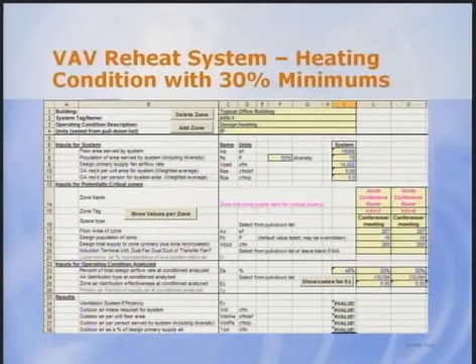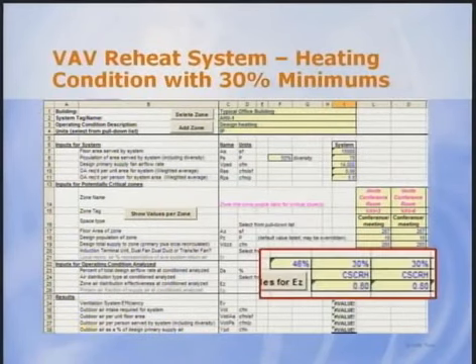First, we'll assume the system is a standard VAV reheat system with 30% minimum set points on the exterior zones. We will assume the interior zones are cooling, but at 75% of their peak, as might occur on a cold morning. On row 23, we enter 30% for the exterior zones and 75% for the interior zones. The spreadsheet automatically determines the primary fan system will be at 46% in cell I-23.